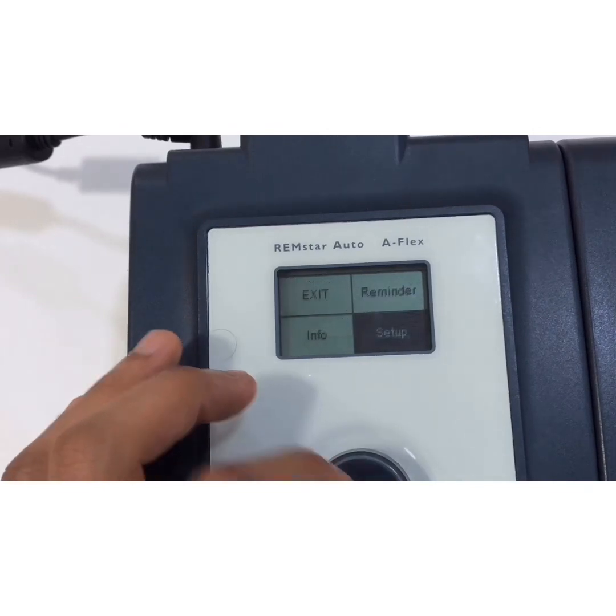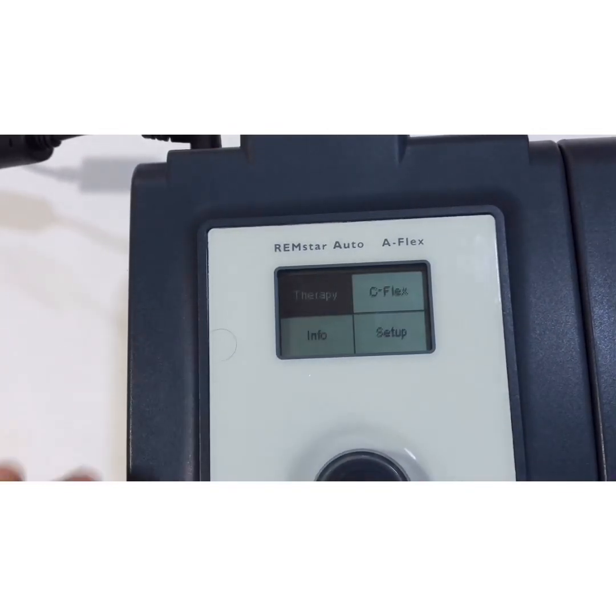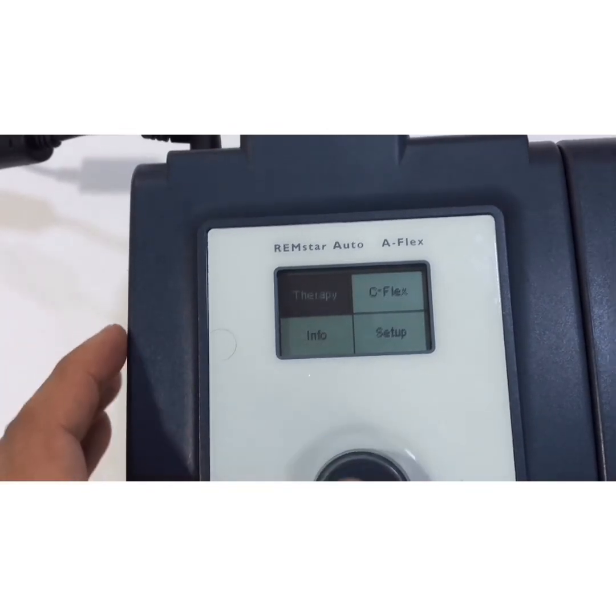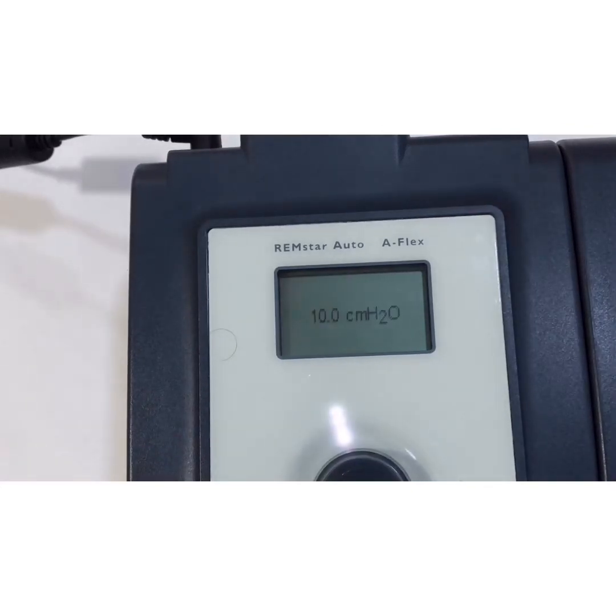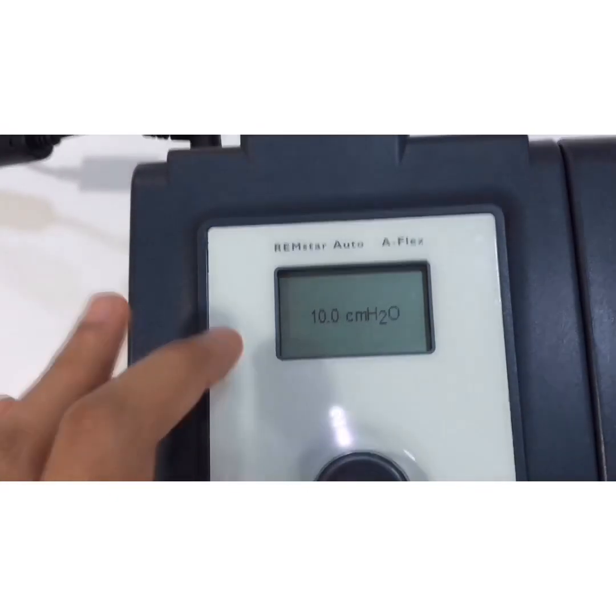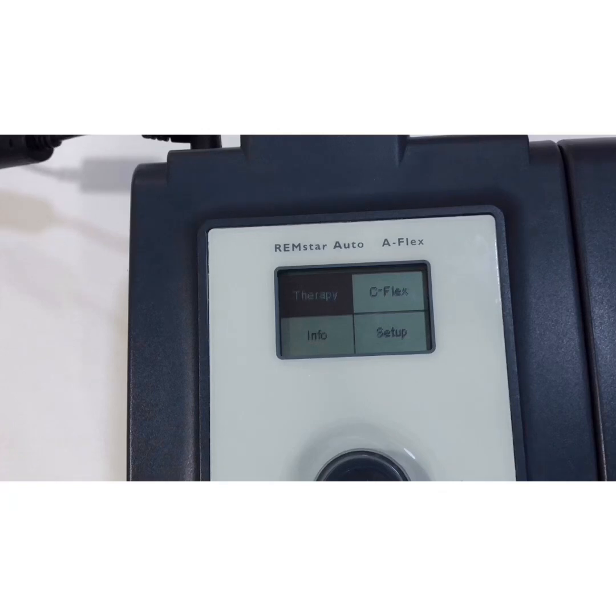So I will go back now to the therapy, and I will start it. As you see, we put the minimum pressure at 10. Then if the patient starts to breathe, the pressure will be adjusted. However, with auto CPAP, the machine will take, I would say, a longer time to adapt to the patient's needs. So the number will be changed over time. It will not be changed immediately.